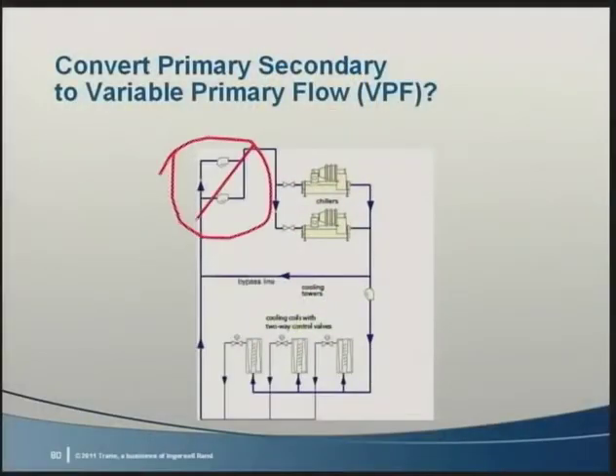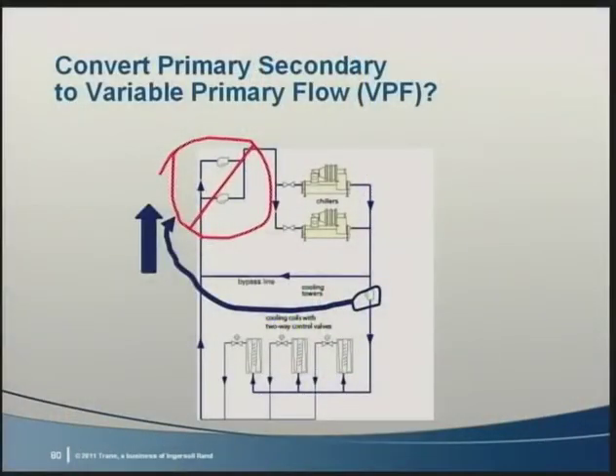Jeannie let me develop my own graphics for this one. First, the primary pumps must all be removed from the system. Next, the distribution pumps must be moved so that they're now on the chiller side of the bypass line. They may also need to be increased in size since they must now overcome the pressure drop through the evaporator bundles. The bypass line is also way too big, so it needs to be downsized for the largest chiller's minimum flow rate, and we need a control valve.